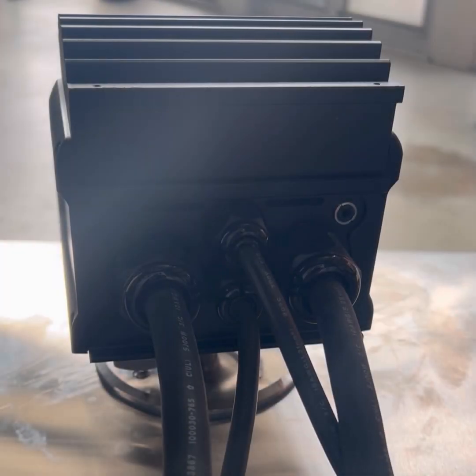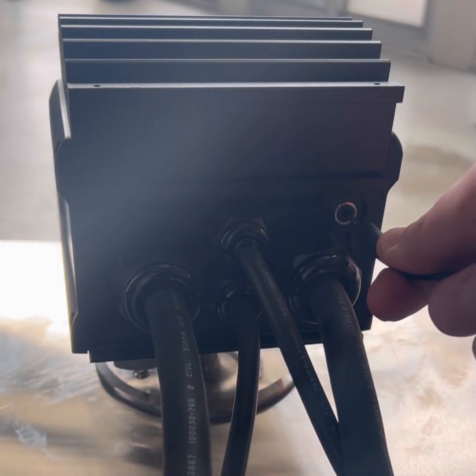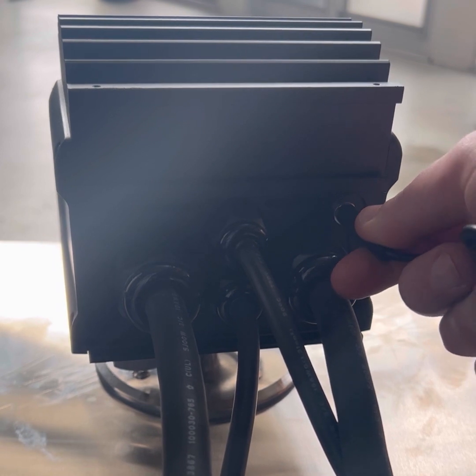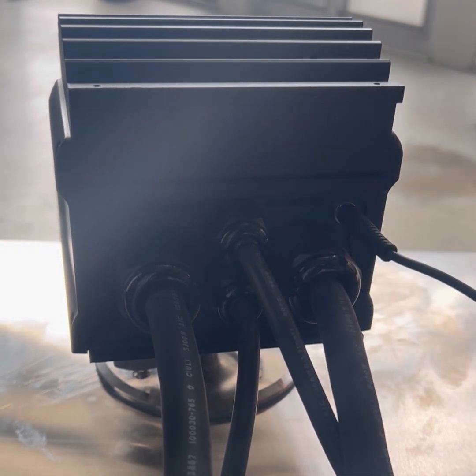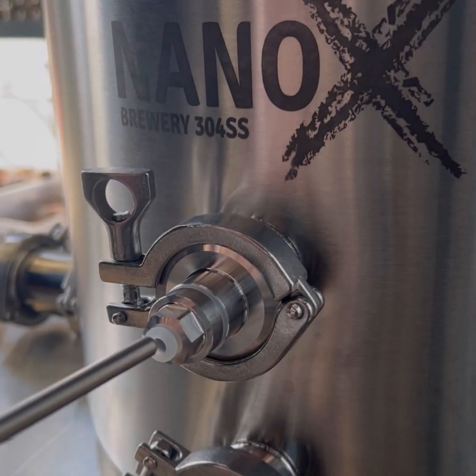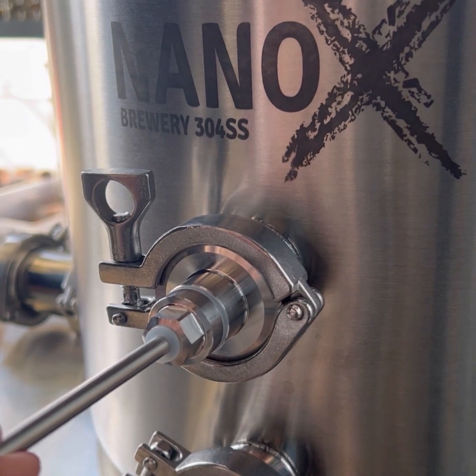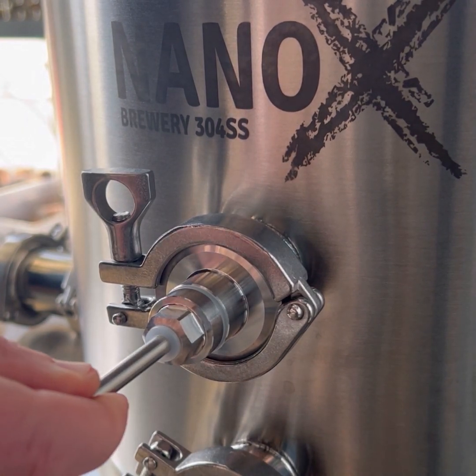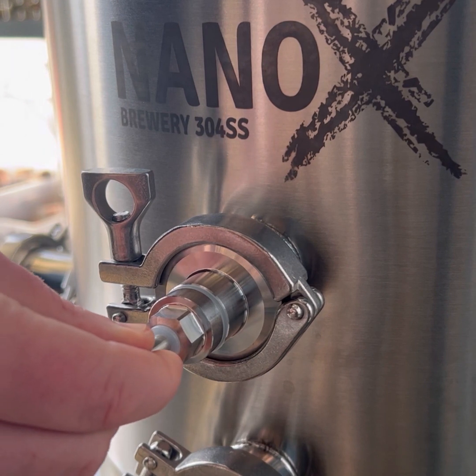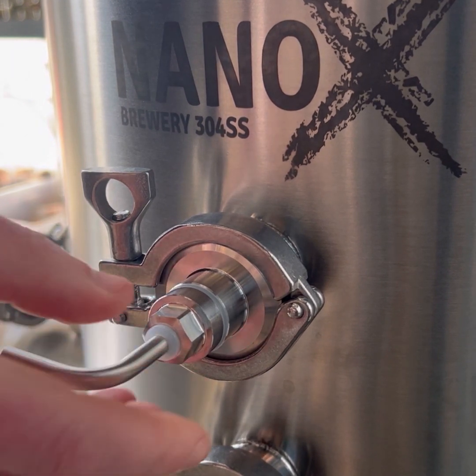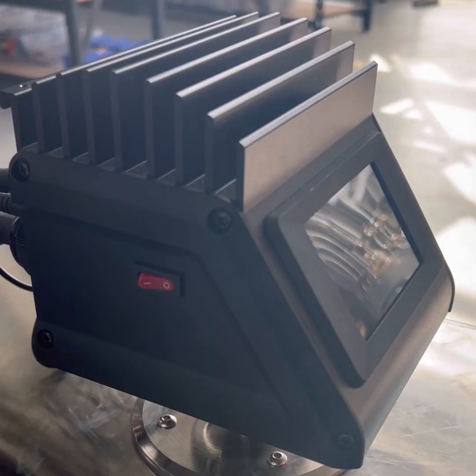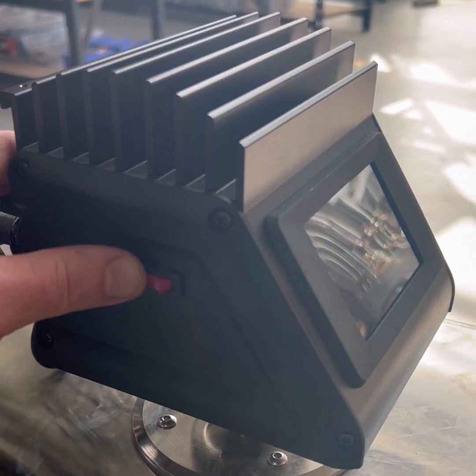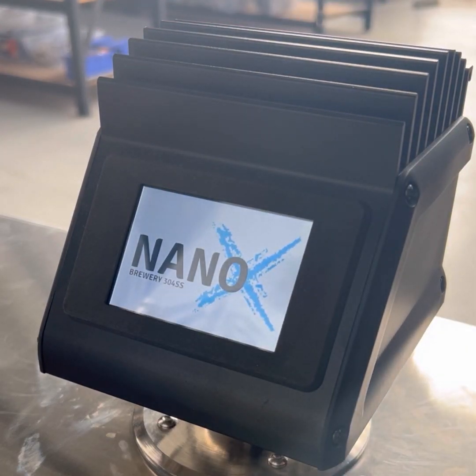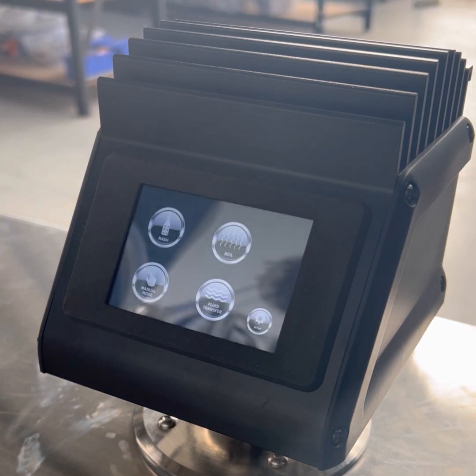Before you turn on your NanoBoss, it's first important to plug in your temperature probe into the NanoBoss and slide the probe into the probe housing located on your dedicated heating vessel. Fill your heating vessel with liquid and ensure the level is above the level of the temperature probe. It's important to note that the NanoBoss can be turned on without being connected to a vessel, but please ensure in this case that you do not have a heating element plugged into the controller.